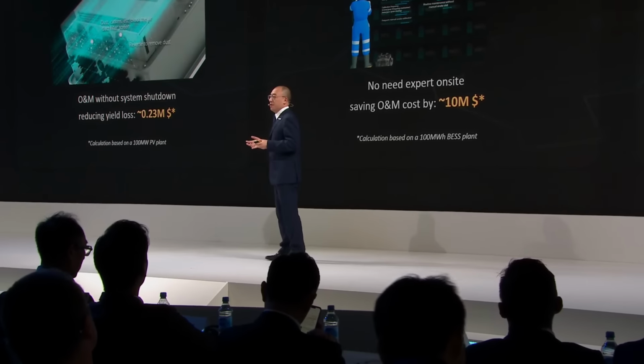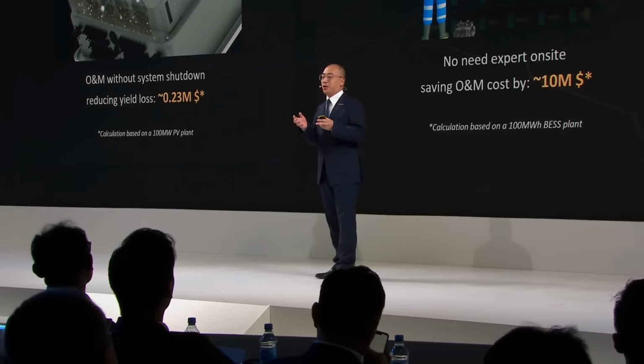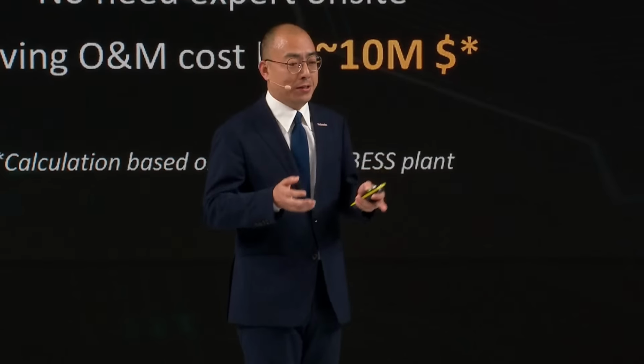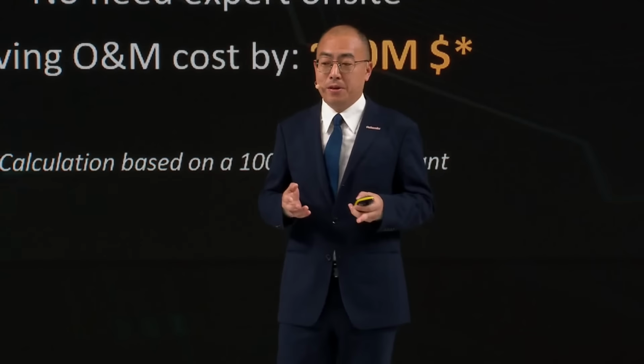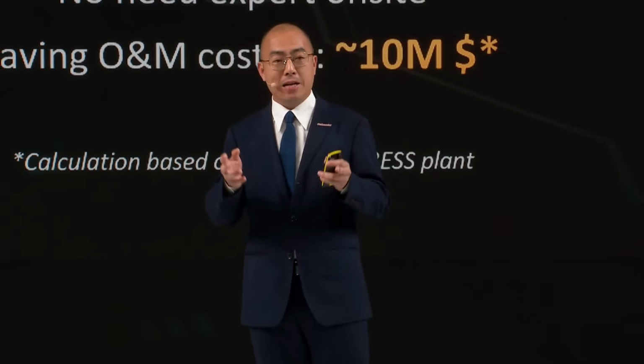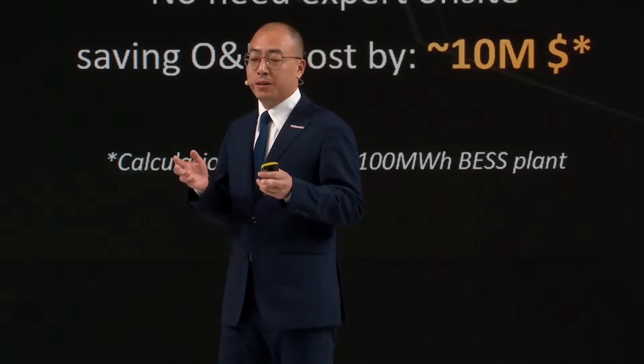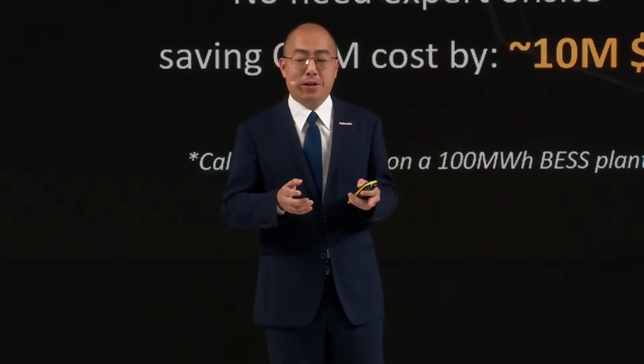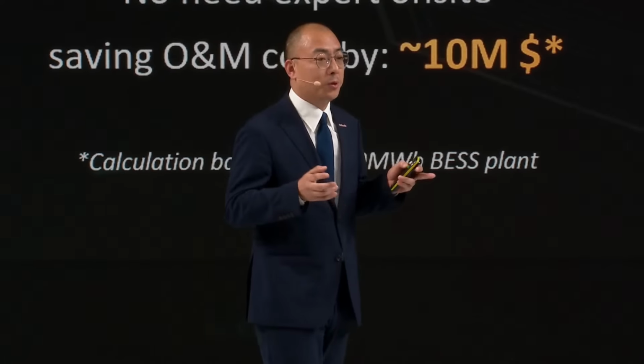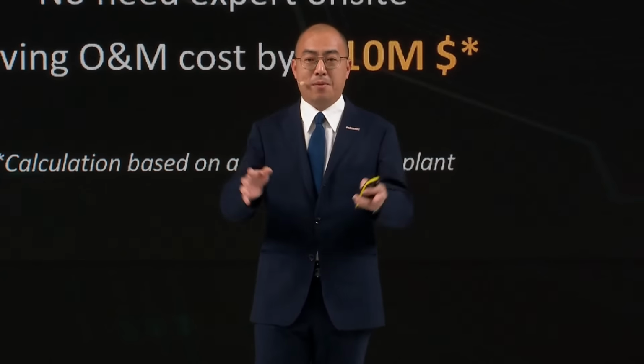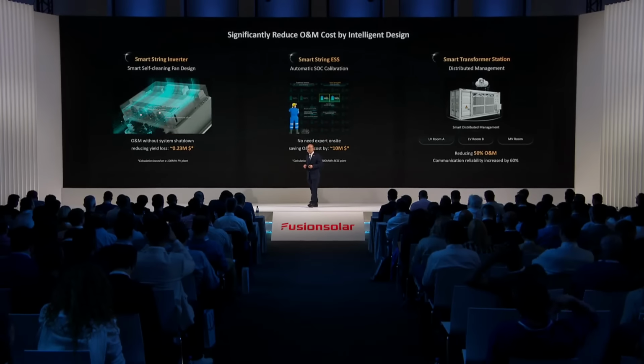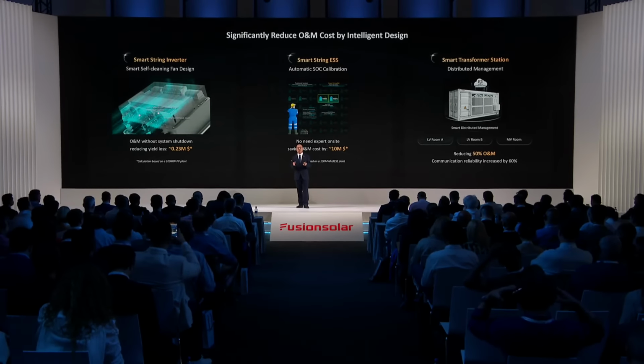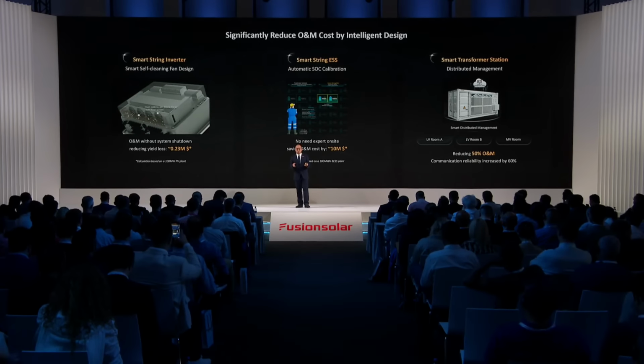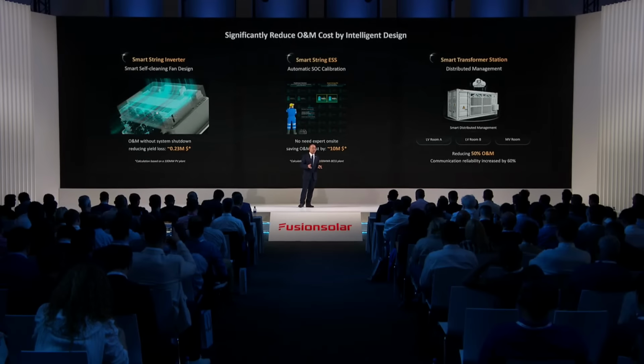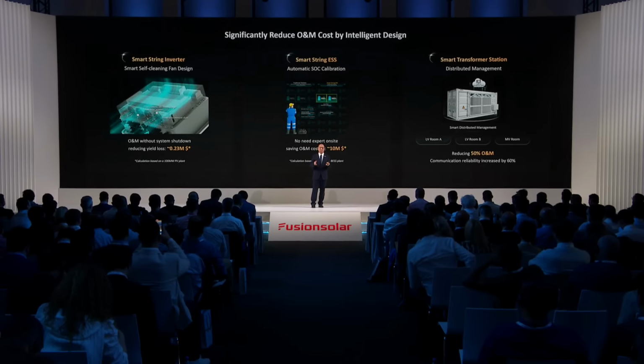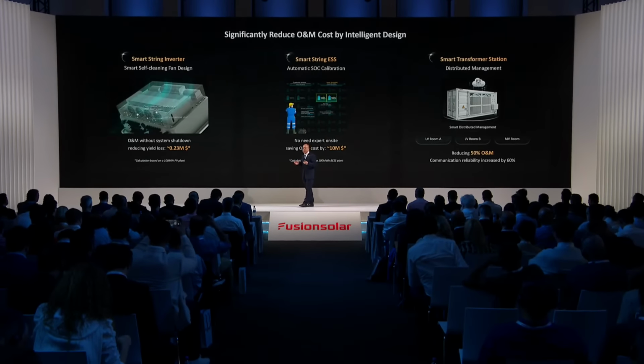For the BESS, while the battery runs for a period of time, the SOC will be inaccurate. The traditional way requires engineers on-site for manual SOC calibration. For a 2 megawatt-hours ESS plant, it usually needs 6 days to do the calibration and needs all the system shut down. Based on the pack-level optimization, smart string ESS could realize automatic SOC calibration, which reduces O&M cost by around 10 million during the life cycle.